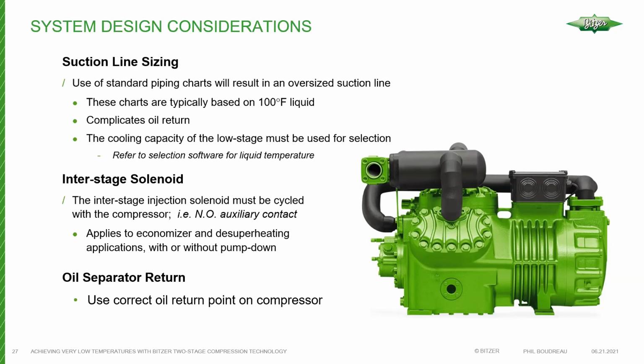Note that the interstage injection solenoid must be cycled with the compressor. So for example, one approach is using a normally open auxiliary contact. That's the simplest way. So if that compressor is running, you need to have interstage cooling. It should never be shut off during any mode of operation while that compressor is running. So this applies to economizing, desuperheating modes with or without pump down.